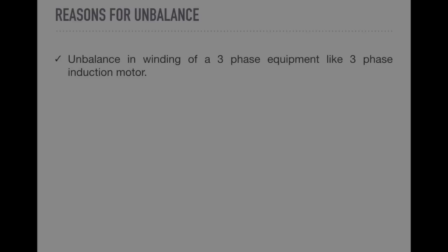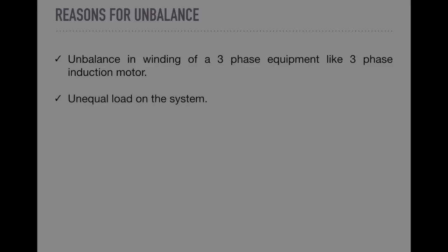Unbalance in winding of a three phase equipment like three phase induction motor. If the reactance of the three windings are not same, then it will draw unequal current from the system. And the second one is unequal load on the system. This causes more current to flow through one particular phase on which the extra load is connected. These are the two main and basic causes of unbalance in a system.